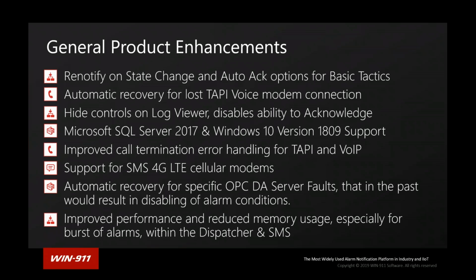Now the problem is you can get in a situation where you may get a bad quality event for an item, but you also, alongside that, get a server fault. And in normal cases, a server fault along with the bad quality is an unrecoverable event, and basically we would normally drop the handle for that item. A simple example is you've defined a tag that doesn't exist in the OPC server. When we ask for a value, a bad quality comes through, but also a server fault that says this tag doesn't exist. We drop the handle on that item. There's no reason for us to keep trying to connect to that forever.